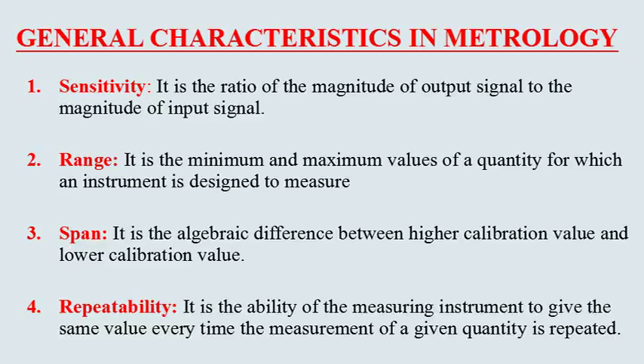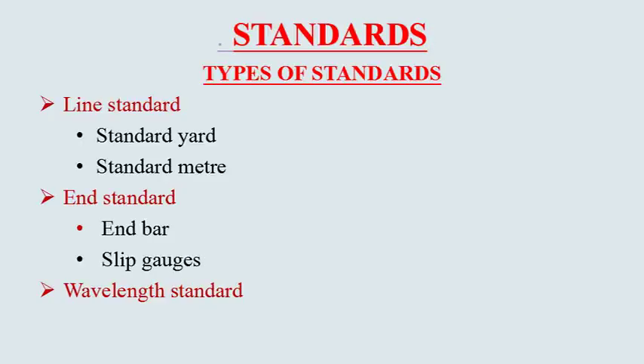Characteristics in metrology: Sensitivity is the ratio of the magnitude of the output signal to the magnitude of the input signal. Range is the minimum and maximum value of a quantity for which an instrument is designed to measure. Span is the algebraic difference between the higher calibration value and the lower calibration value. Repeatability is the ability of the measuring instrument to give the same value every time the measurement of a given quantity is repeated.